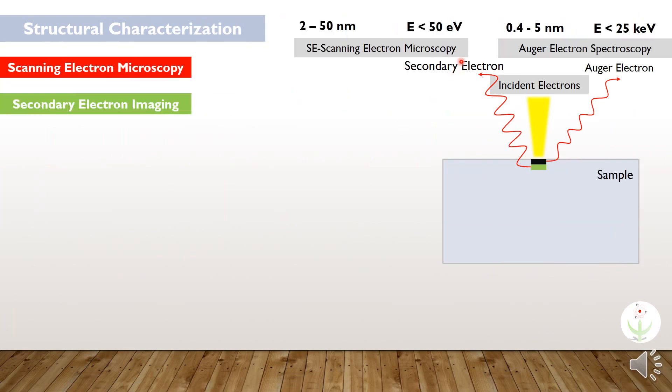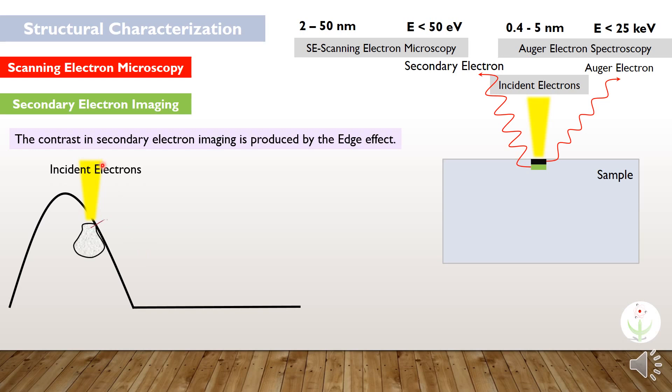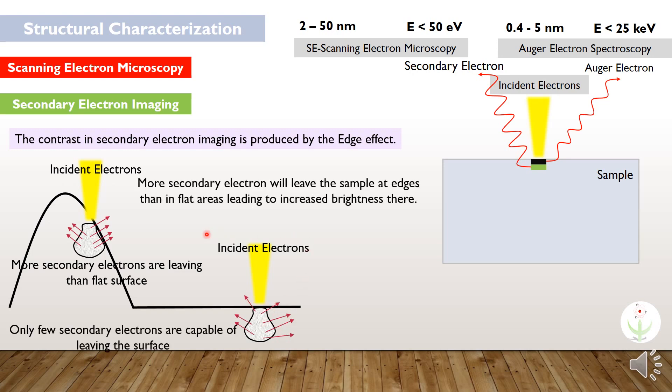These secondary electrons provide information about surface morphology and topography as they are coming from the top few nanometers. Now, the question is how do secondary electrons produce dark and white contrast in the images? The answer is the edge effect. To explain this effect, let's imagine a surface having edge and a flat part. When high energetic electrons strike the edge part, you can see how electrons are emitting from the surface. But in case of flat surface, only few electrons are capable of leaving the surface. That is why more secondary electrons leave the sample at edges than in flat areas leading to increased brightness there.